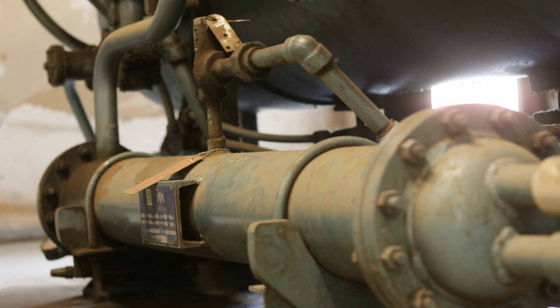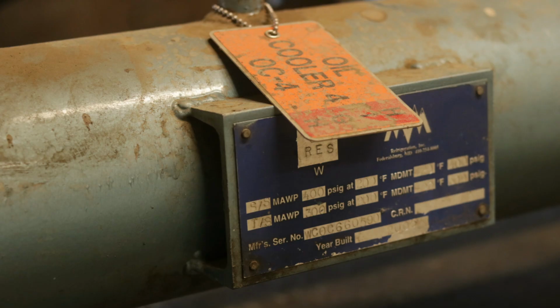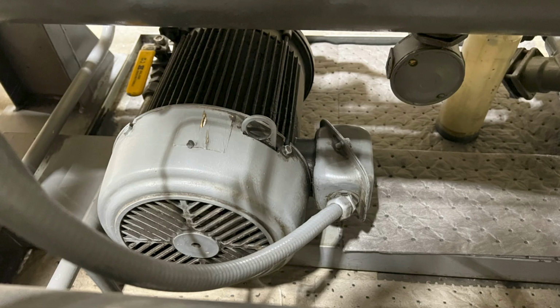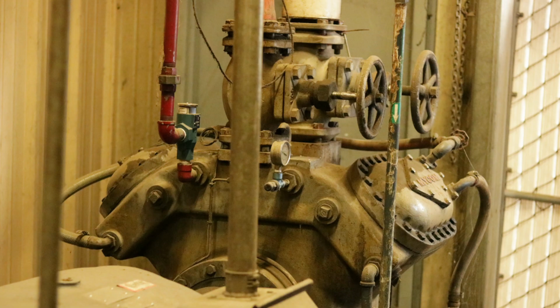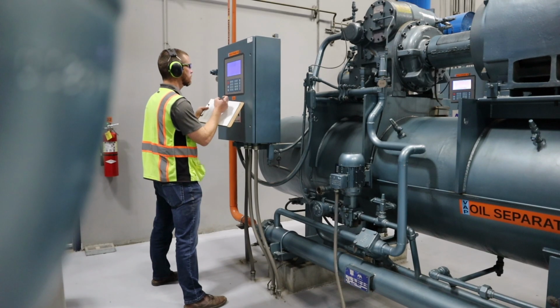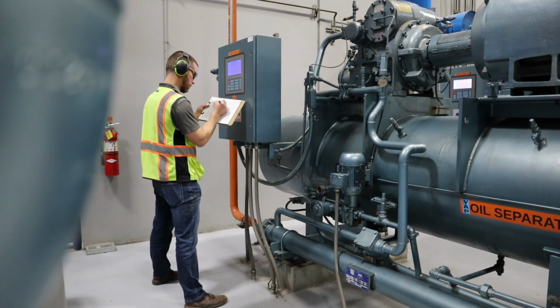Next, the operator must verify the ancillary equipment such as oil cooling system and oil pumps are ready for operation. These will vary from compressor to compressor, so the operator must have access to the original equipment manufacturer or OEM instructions. Finally, the operator must confirm the compressor suction and discharge valves are open. Once these steps and other site-specific procedures are followed, the compressor can be started.